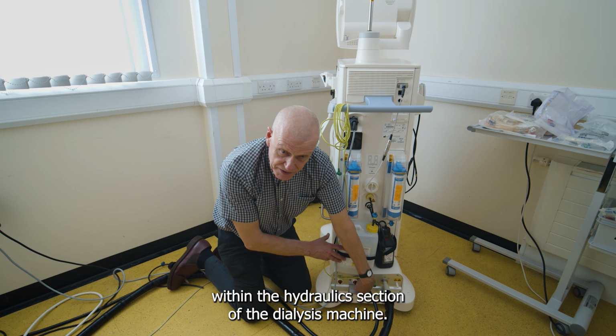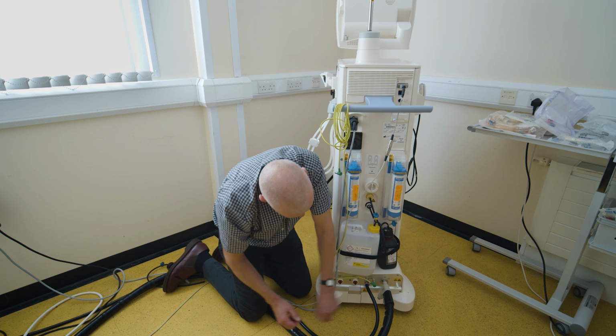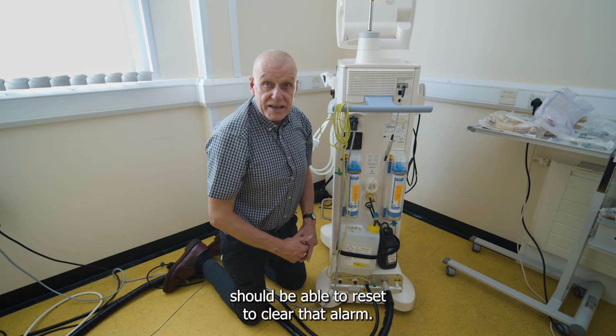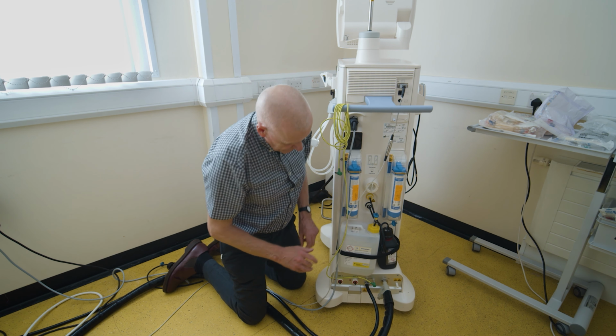this sensor pot here. The way to clear that alarm is to get a syringe in here and draw the fluid out, and then wipe it clean with a paper towel, close the flap, and the machine should be able to reset to clear that alarm. It's sometimes difficult to find this flap, but if you locate it next to the drain, under this point here, that little flap there will just lift up and you can clean the fluid out.